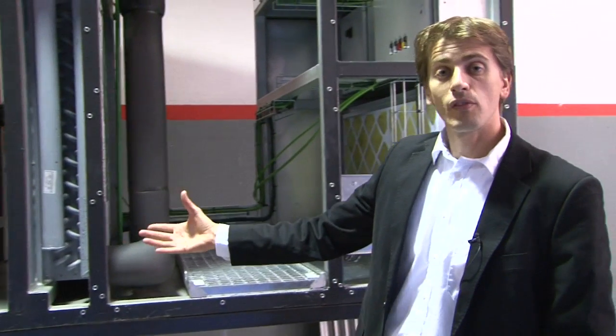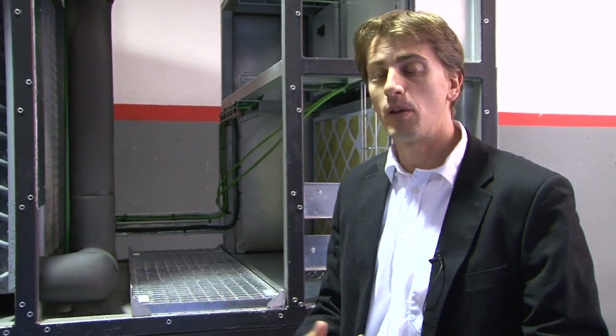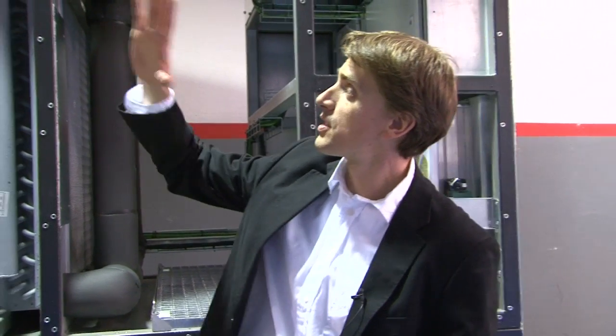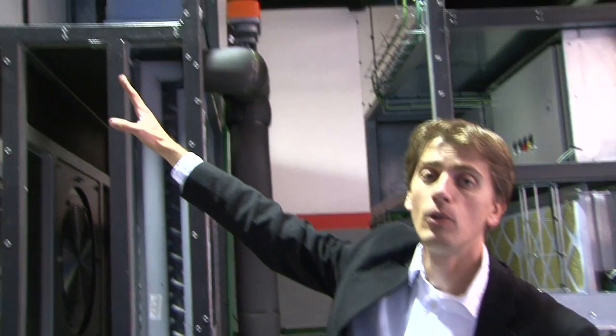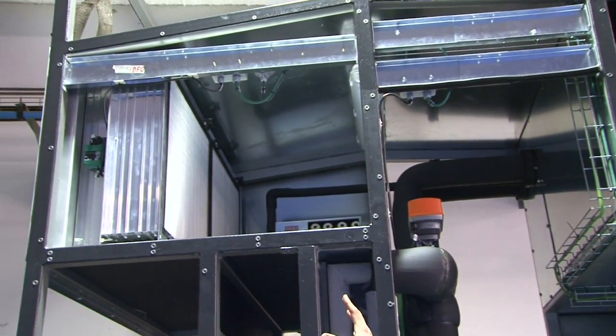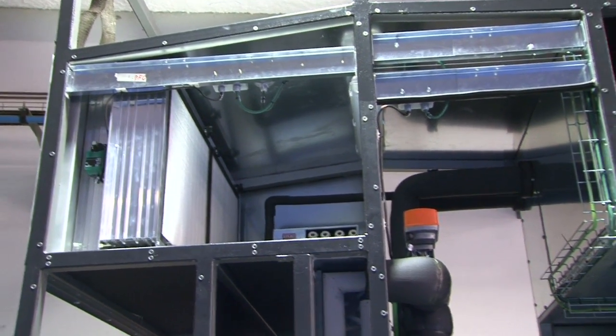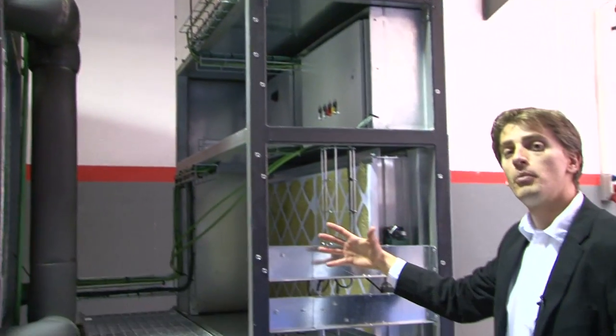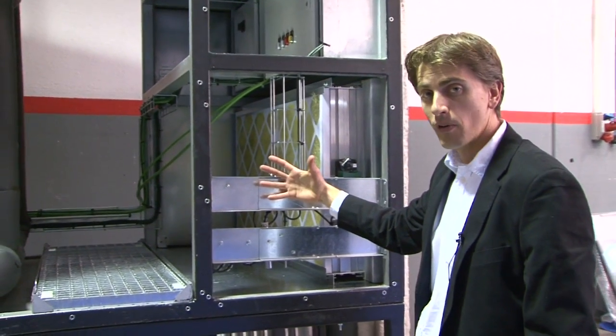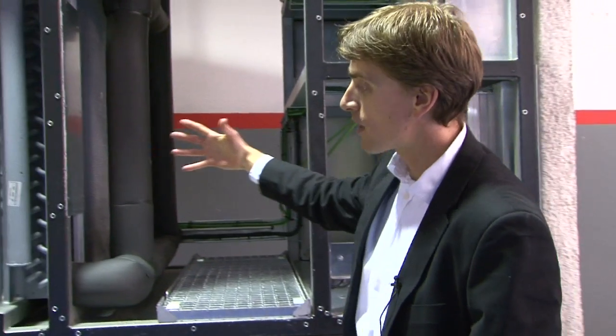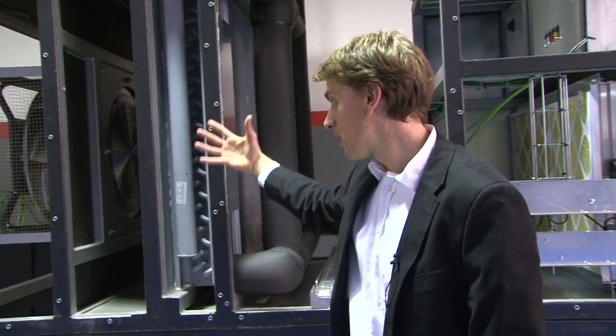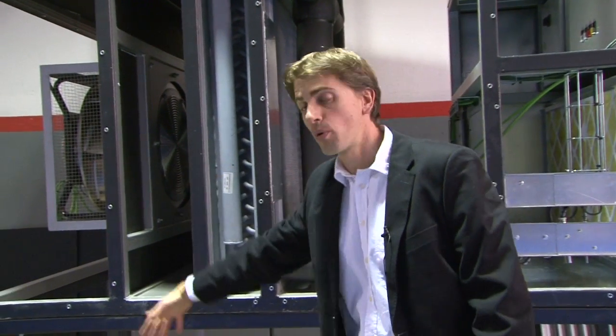The third stage of operation would be whenever we have high temperatures on the outside. We cannot cool down our servers anymore, so what the system does is basically shut down the louvers. We are not using external air anymore. We will be capturing all the hot air provided by the hot corridors from our data center towards our coils, then cool down the temperature and provide it again towards our raised floor.